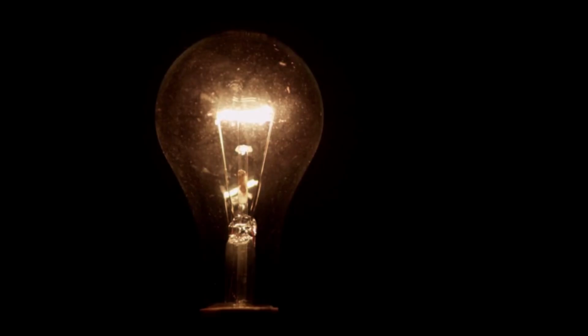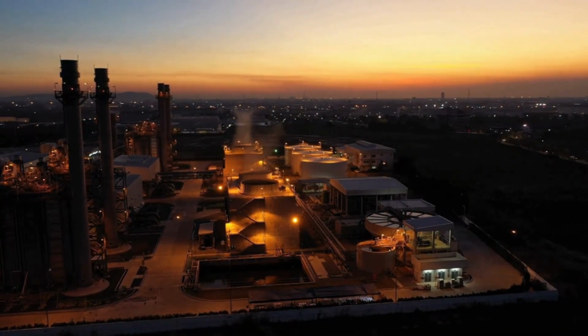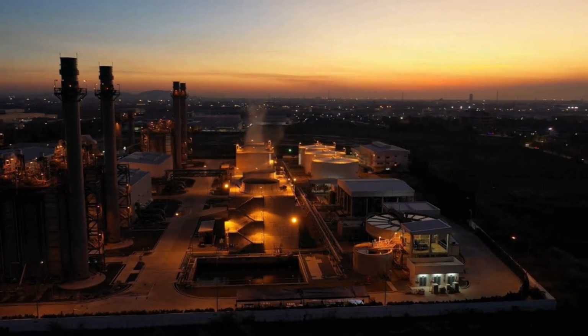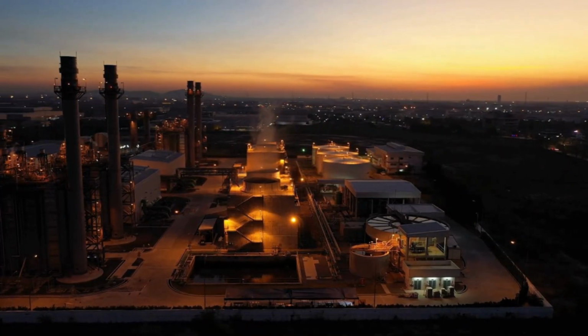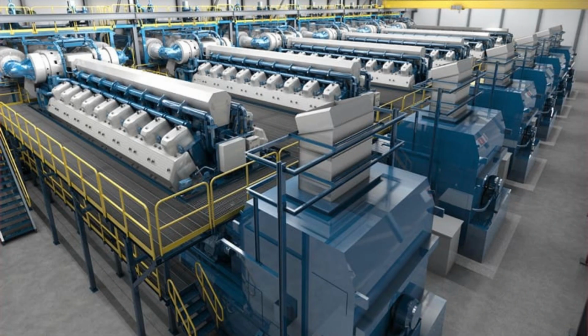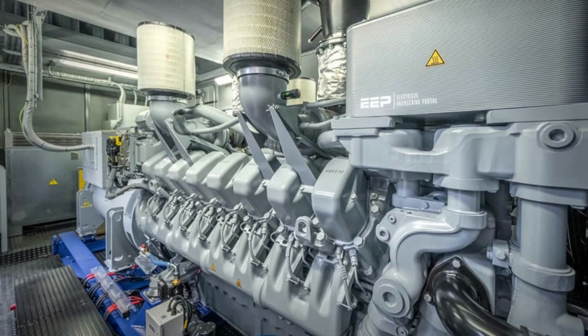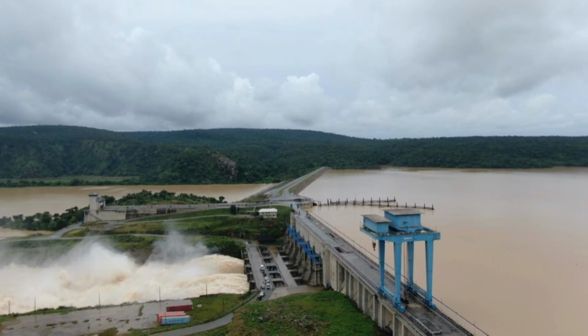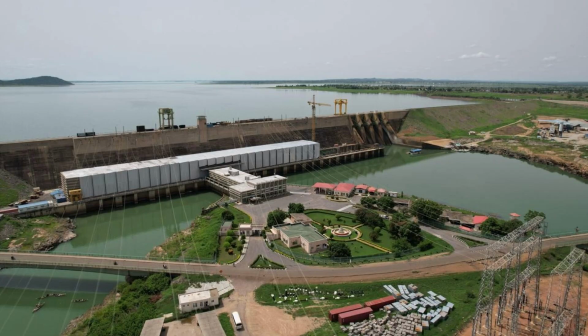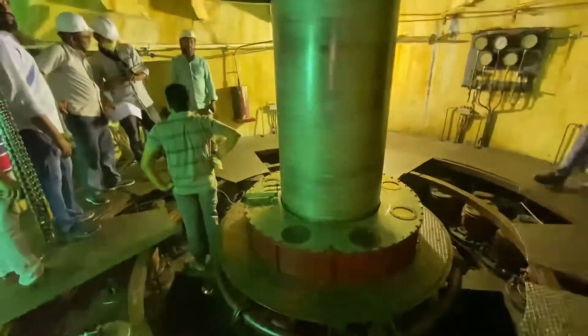When the grid collapses, restarting it isn't simple. Power plants need electricity to start, but with the grid down, that electricity is unavailable. This is where the black start generator, which is the backup generator for power plants, comes in. Certain stations, usually hydroelectric plants like Shiroro and Kainji, can restart without any external power.